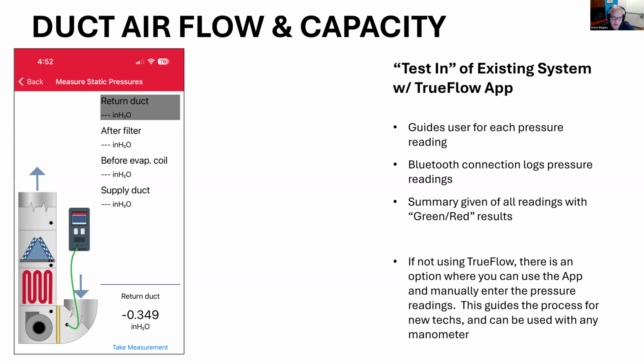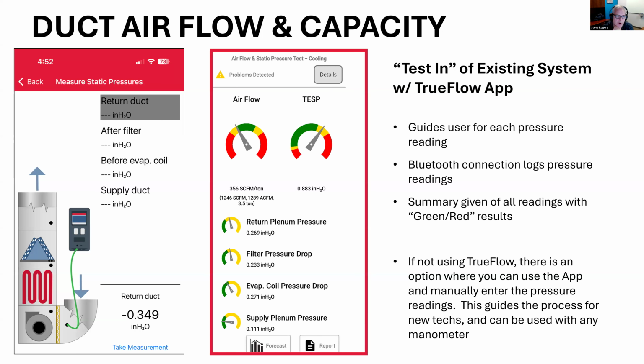And then the result of that is a report that looks like this. The two main dials are airflow and static pressure. That's the main thing about airflow: am I getting enough flow or too much or too little? And how's the static pressure? You can see that this system that we evaluated, airflow is a little too low. We're below the green zone. We're into the yellow caution zone. And the static pressure is really too high at 0.88. Most manufacturers would not recommend that much static pressure.